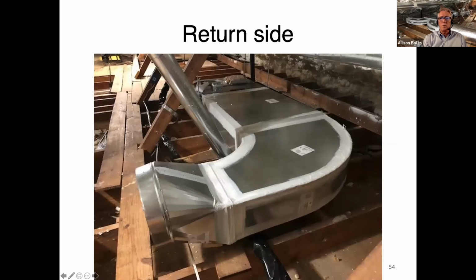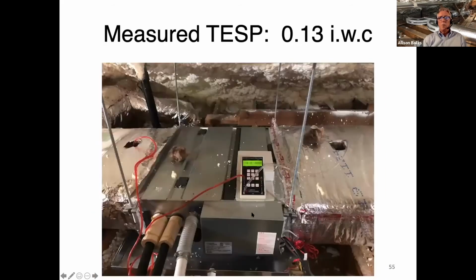You've seen this one before. So it works really well. And the total external static pressure on this is 0.13. So a little bit higher than the one at the office, but there's more ductwork here, more fittings. You'd expect it, but still it's rated for 0.2 and we're running at 0.13. Hey, I'll take it.